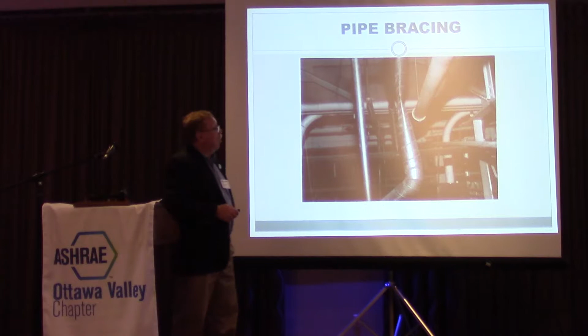Here's a clevis that has to be replaced. The piping system is probably still up and running, but this clevis needs replacing. What happened to it? The assumption is the pipe saw a vertical input, went up, hit the center of the cross bolt, bent the bolt upwards, came back down, and the rest of the clevis slid down to its lowest point. This has got to be replaced, and it's not easy to replace a clevis after it's installed. You basically have to go up there, support this pipe, and take the whole thing apart.